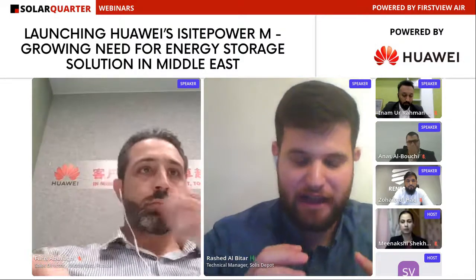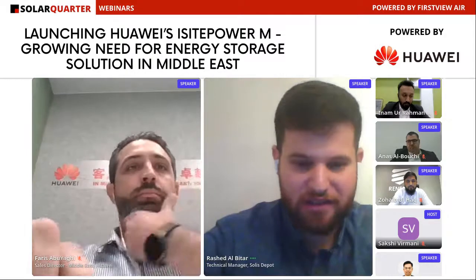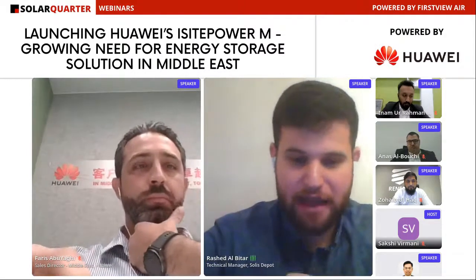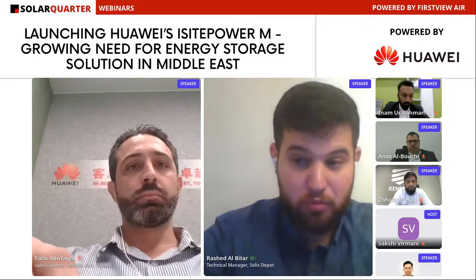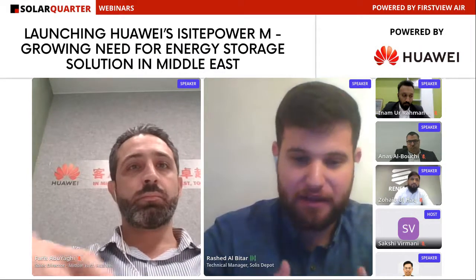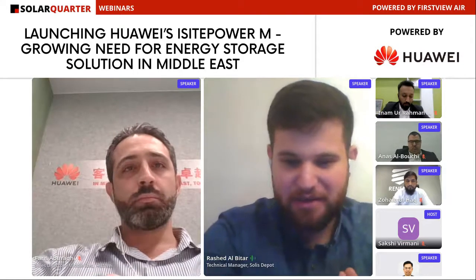The third layer of protection, as Cornell has said, is basically a fire extinguisher bag inside each battery module. Whenever the temperature sensor reaches around 170 degrees Celsius, this fire extinguisher bag is activated. It will blow up and turn off any fire that might happen on our site. This is the battery chemistry in three layers.